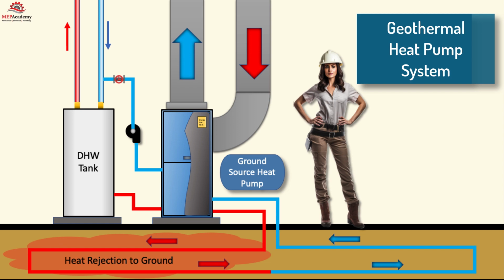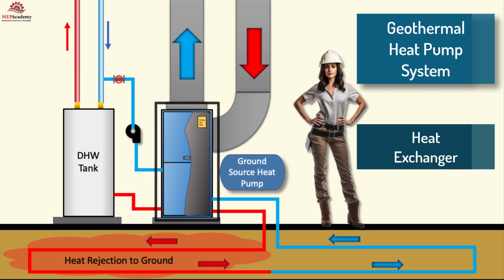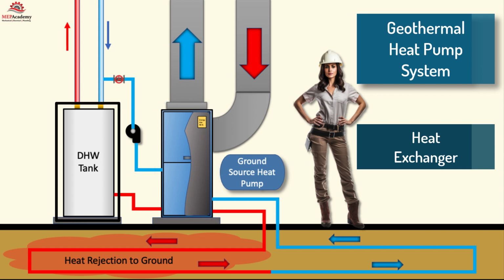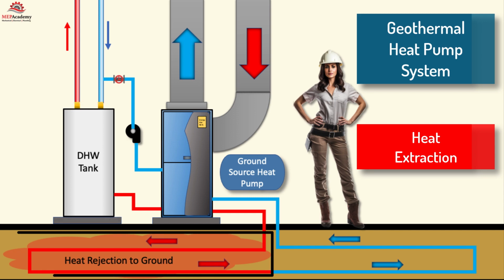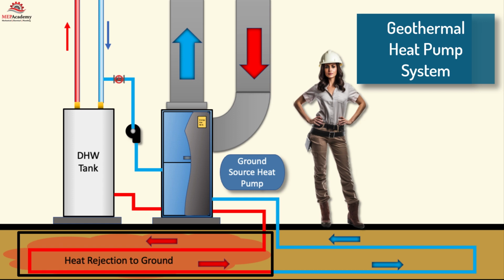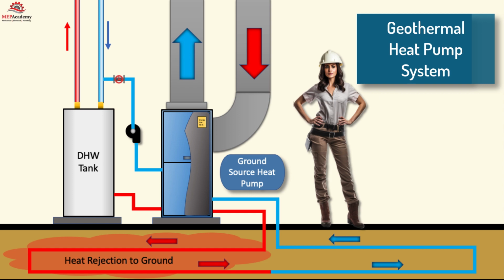1. System setup. The desuperheater is integrated into the geothermal heat pump system. It consists of a heat exchanger, a control valve, and a separate storage tank for hot water. 2. Heat extraction. During the cooling mode of the geothermal heat pump, excess heat is generated and normally dissipated into the ground. Instead, the desuperheater diverts this excess heat from the heat pump's refrigerant to the heat exchanger.